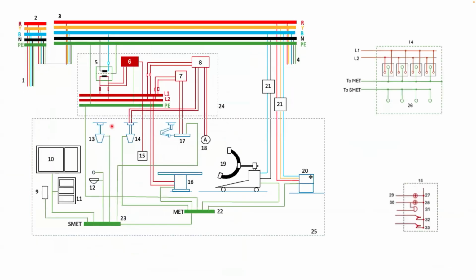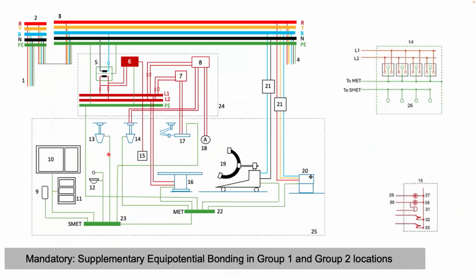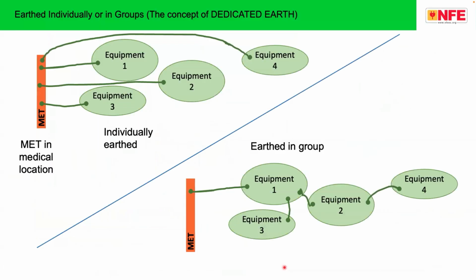Similarly, for the operation theater, a mandatory safety measure is supplementary equipotential bonding, means you must bond again. Additionally, you must bond all the metal parts inside the group 1 and group 2 location so that the patient is not getting a shock. There is no chance of arcing, there is no chance of fire, and so on.